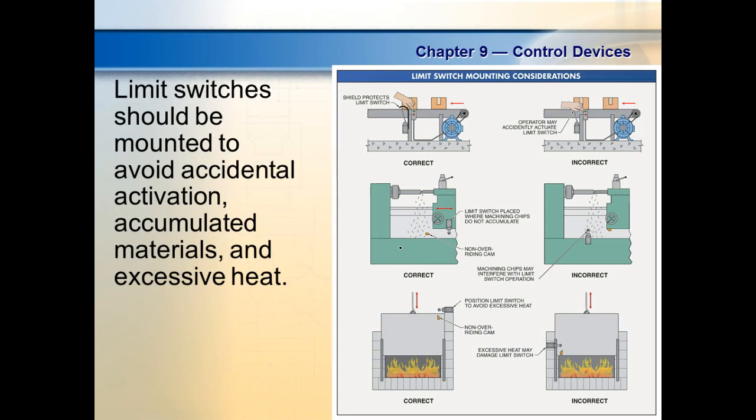So here they was actually depending on the part that's moving. Here they mounted the limit switch on what's moving and they put the stationary cam at it, right? And then of course the next one should be obvious. What's wrong with the one on the right? Right above the fire, yeah. So what they did is they moved it to the top.